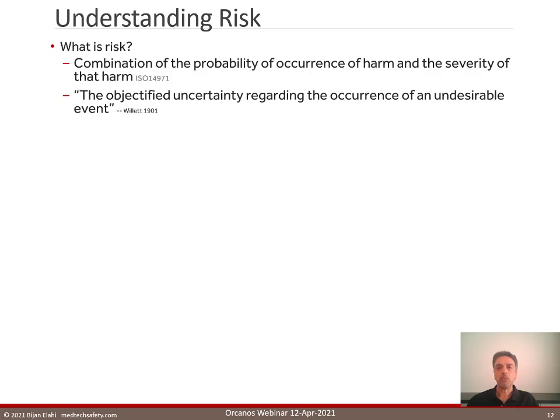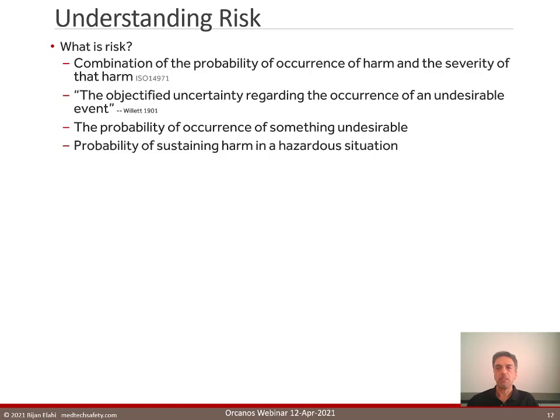The language of Alan Willett's definition is antiquated. This is a more modern restatement of the same thing. The risk is the probability of occurrence of something undesirable. For the medical device industry, this is a better definition. Risk is the probability of sustaining harm in a hazardous situation. Because it uses two key terms from ISO 14971, harm and hazardous situation.